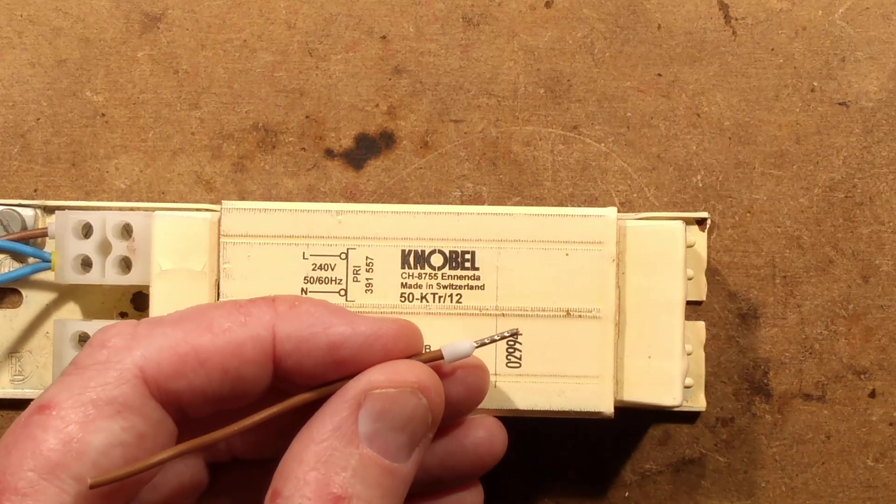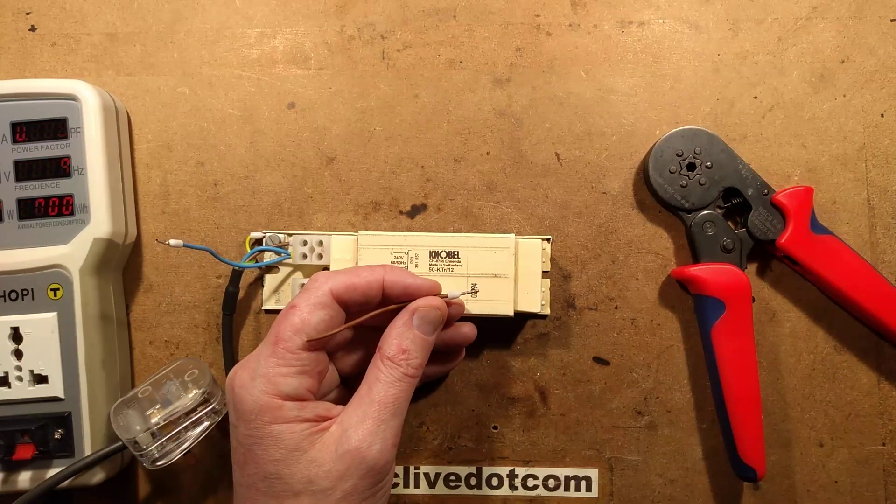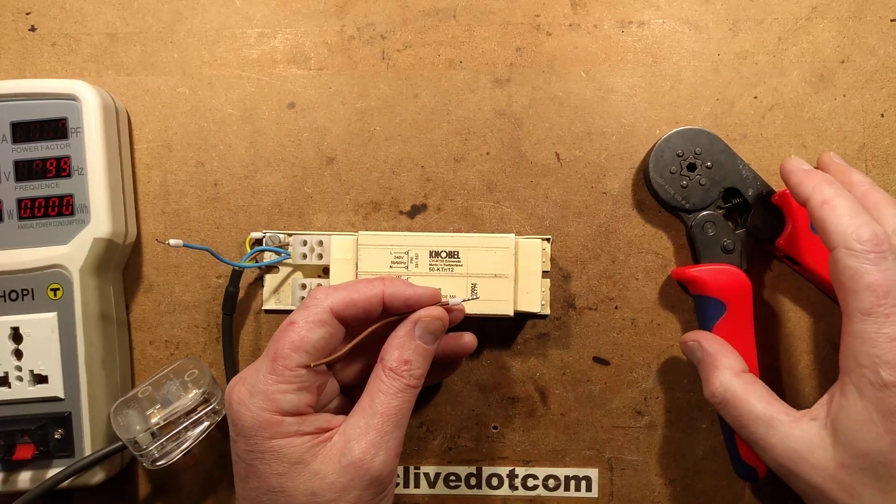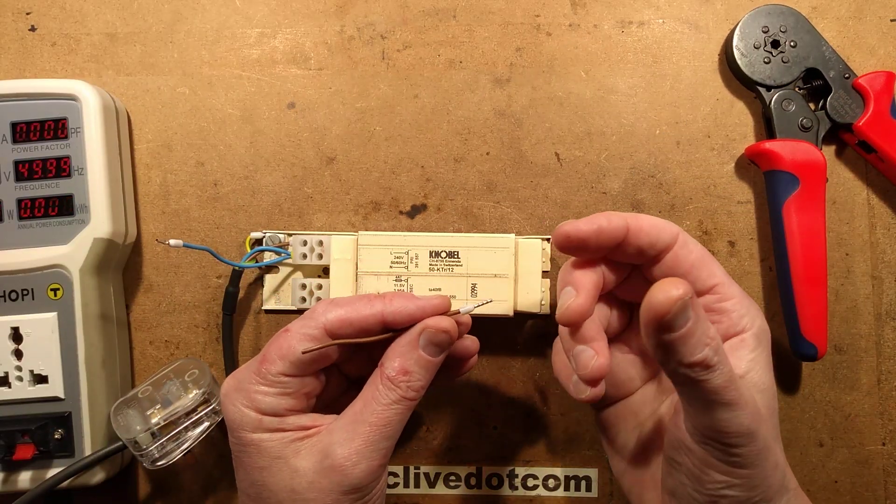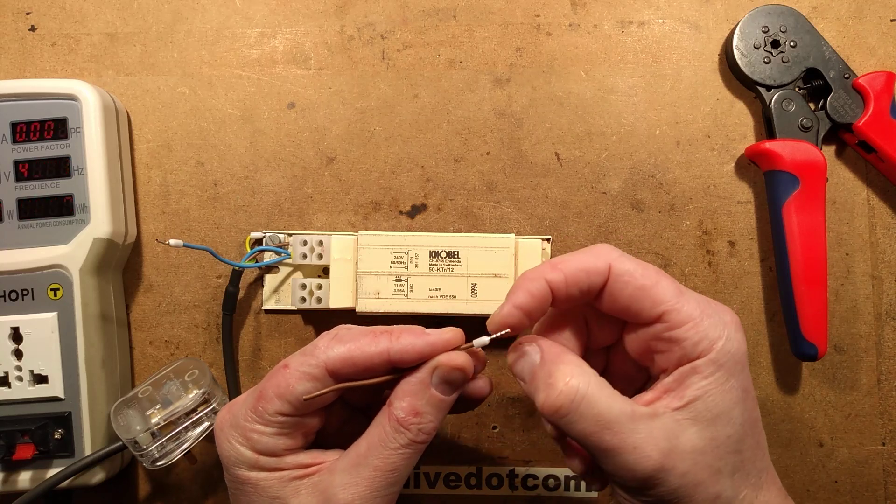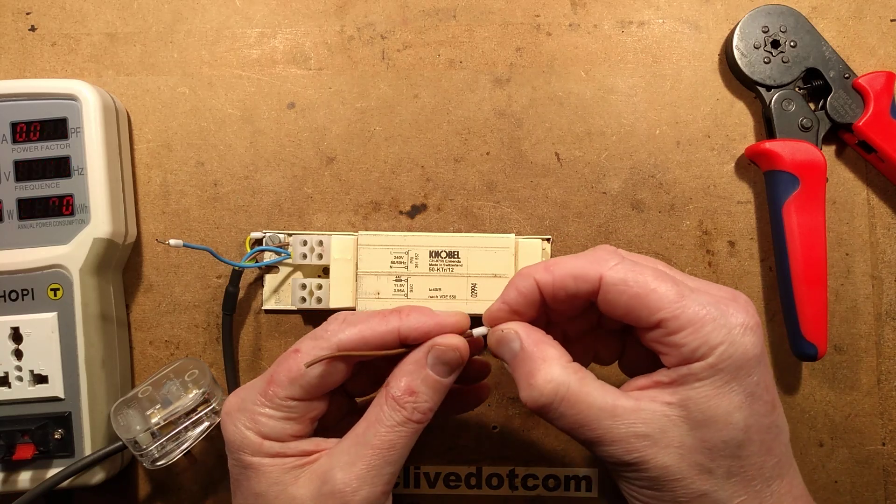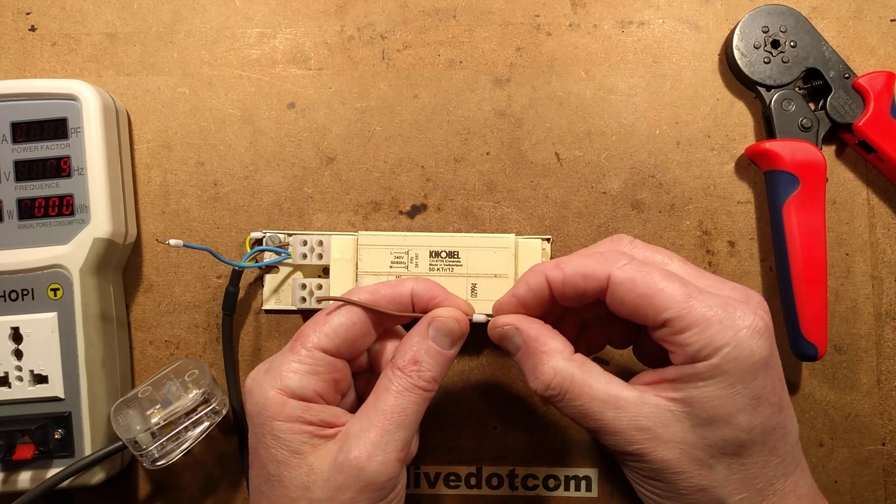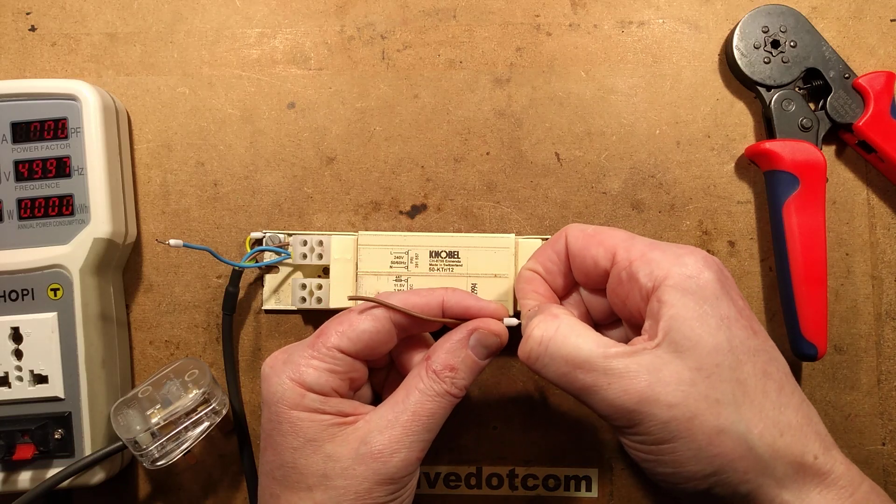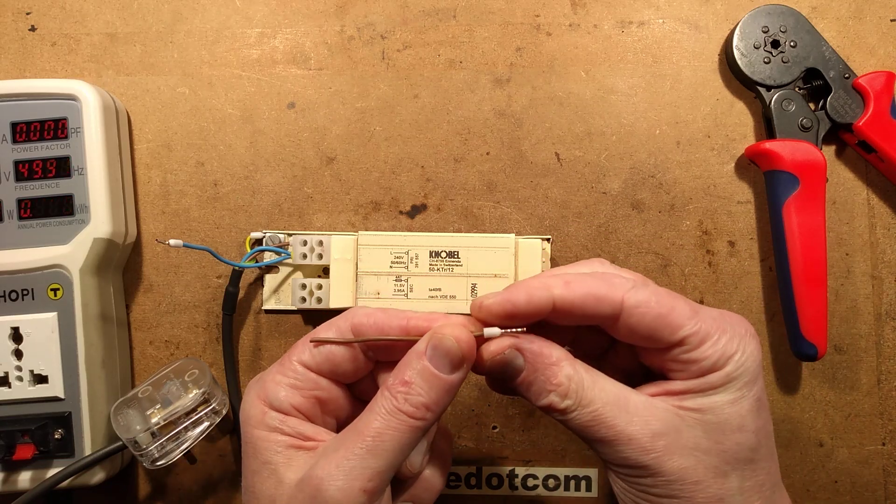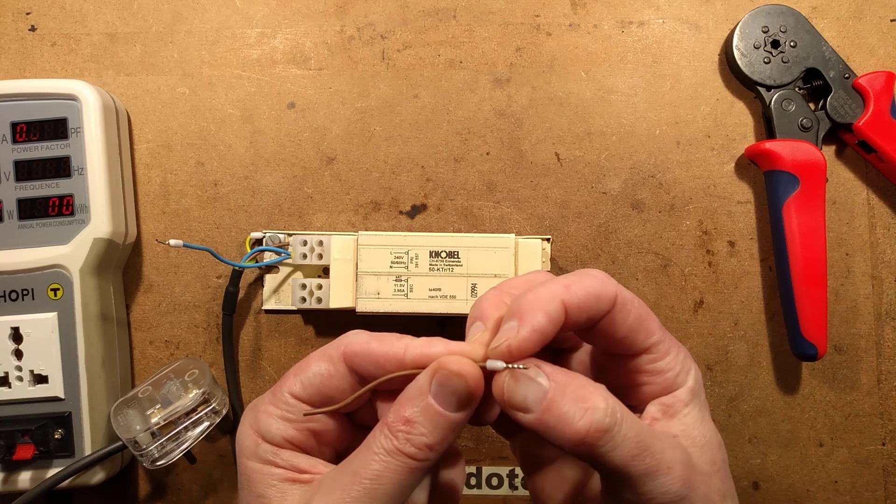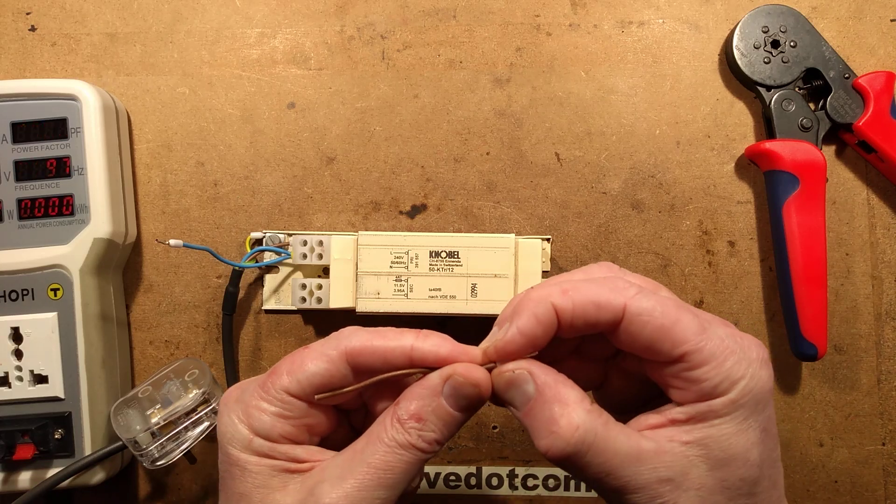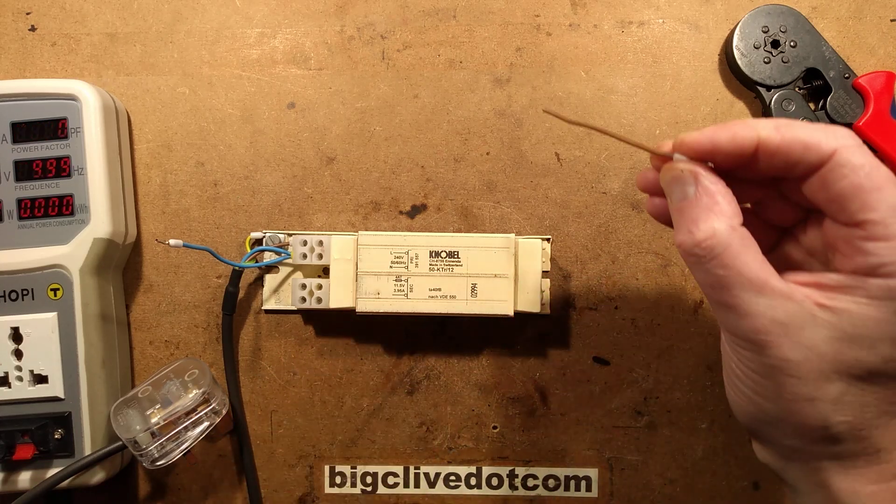And the ones I used to use, I used to put ferrules in all the cables in my control panels, was just the traditional plier that just puts little indents in. But if you consider it, it's not that critical because once you've put it into the terminal, the terminal itself actually displaces the metal down anyway. But this is quite a nice finish. This is quite neat. It has put those little indents all around it and it seems to be quite secure.